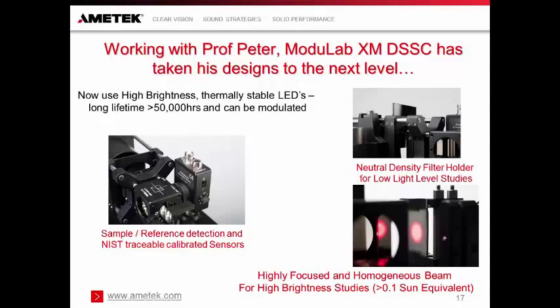the device under test. The critical thing here is that the distance between the reference detector and the beam splitter, and the distance between the solar cell and the beam splitter, are identical. Therefore, the intensity measured by the photodetector and the intensity measured by the cell are exactly the same. And that's how we generate a good reference signal. This is described as a fixed position optics system, and I should explain that in further detail in a moment. But in essence, there is no need ever to change the position of the reference photodetector with respect to the solar cell. Therefore, the chances of introducing unwanted errors are very low.